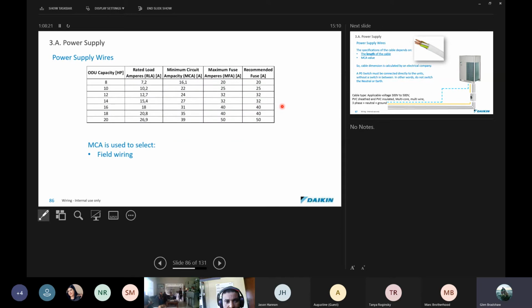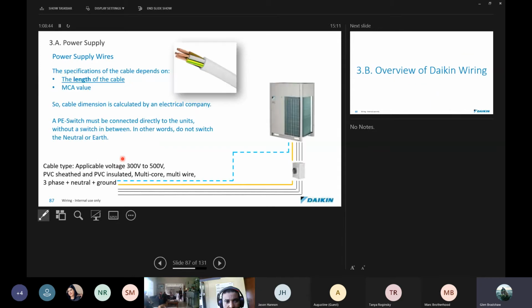Supply wires, the MCA. So we use the maximum fuse amperage for the circuit breaker. We use the minimum circuit amperage for selecting the field wiring. And this can be selected off of SANS tables or off of the supplier tables for the particular wire. They must be in accordance with the SANS as well when using them. Power supplies, the specifications of the cable depend on the length of the cable and the MCA or minimum circuit amperage value. Cable dimension is calculated by an electrical company. In other words, an electrical engineer should be doing that.